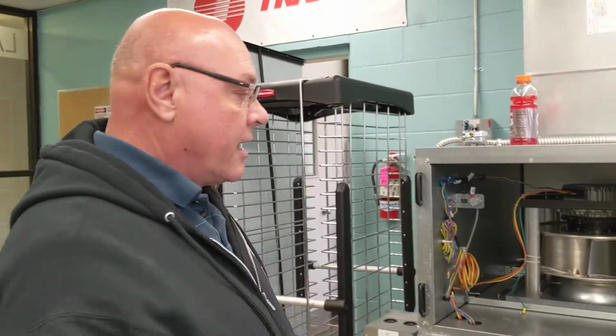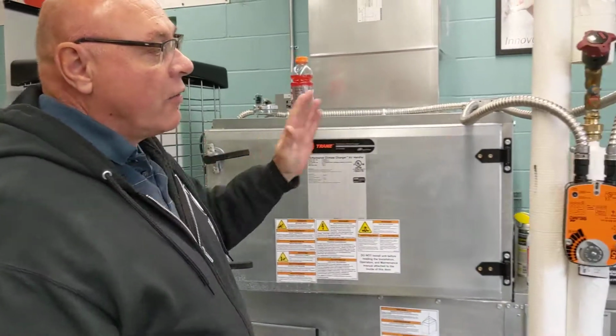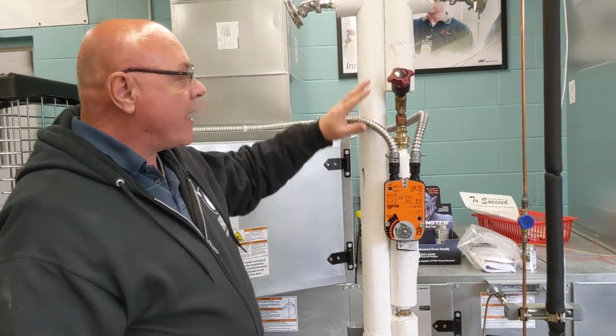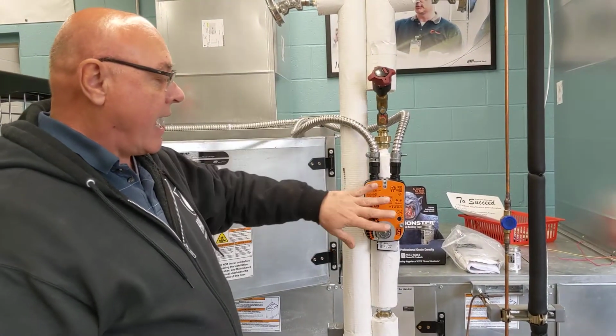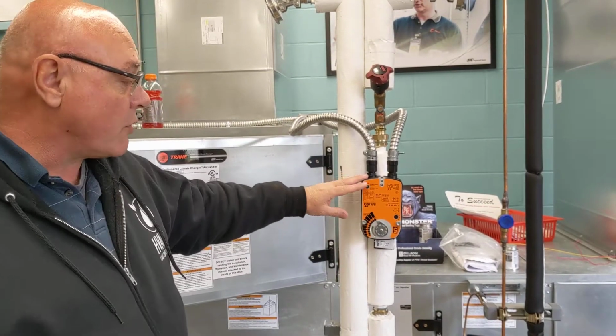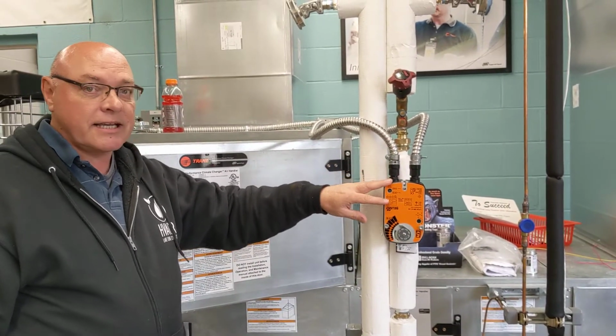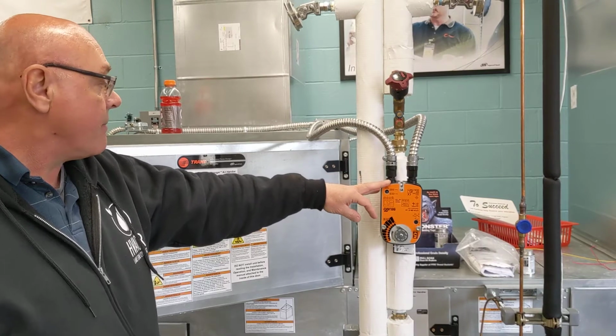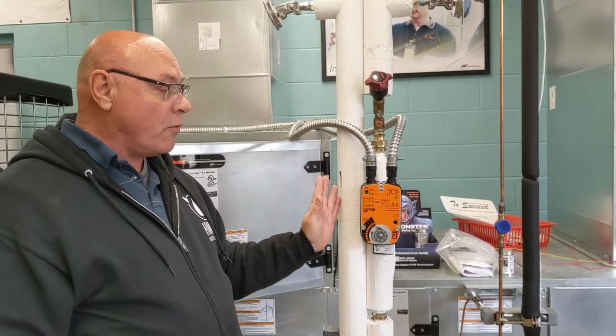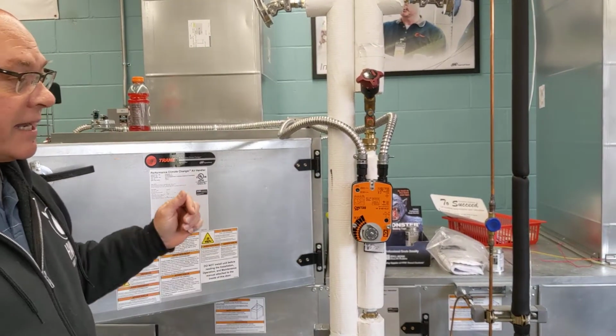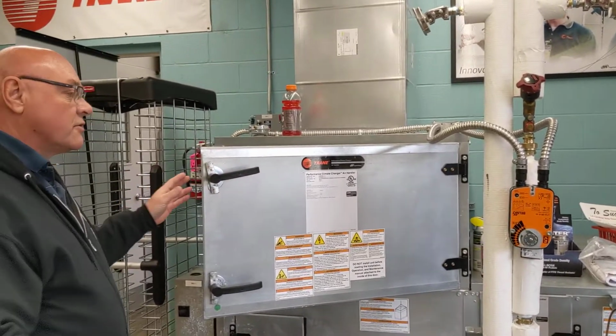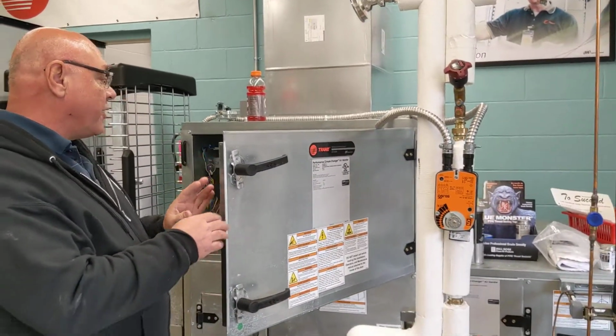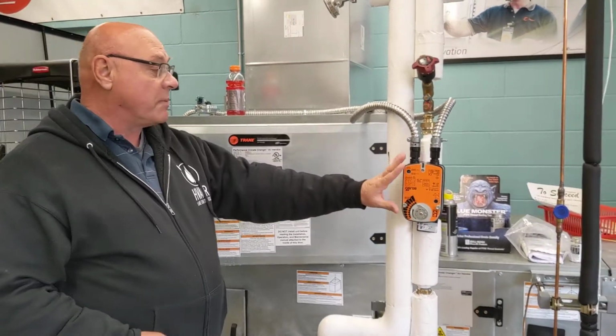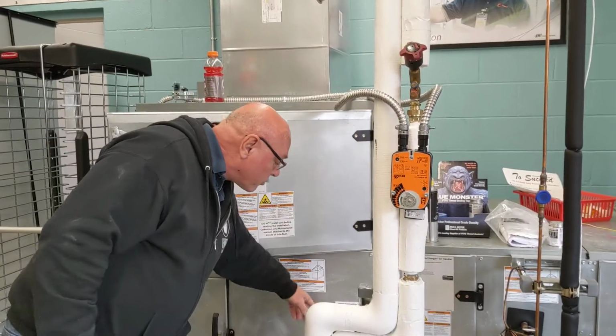for heating. So here we're controlling our heating by a balancing valve and a control valve. The control valve here gets a signal from the thermostat basically telling how far we're going to open or close this valve, all depending how much heat we need. So if we're bringing in outside air and we only need a little bit of heat, this will be barely open. It'll go through our coil.